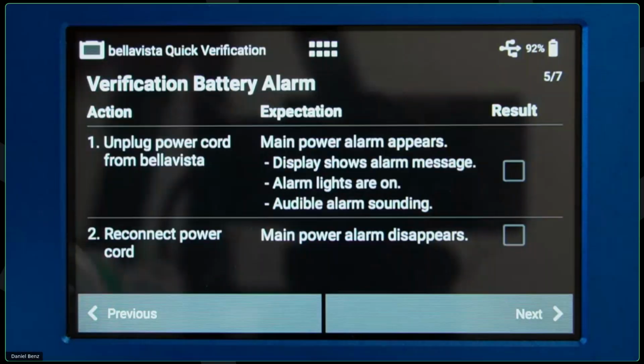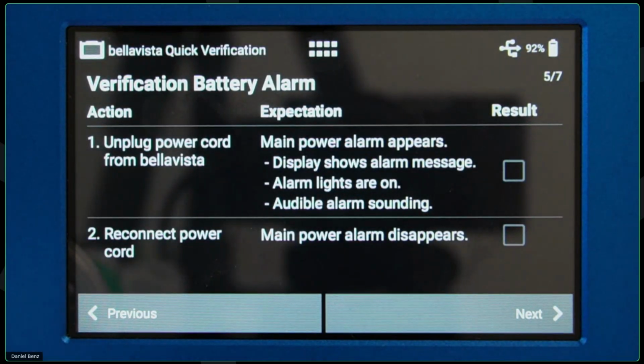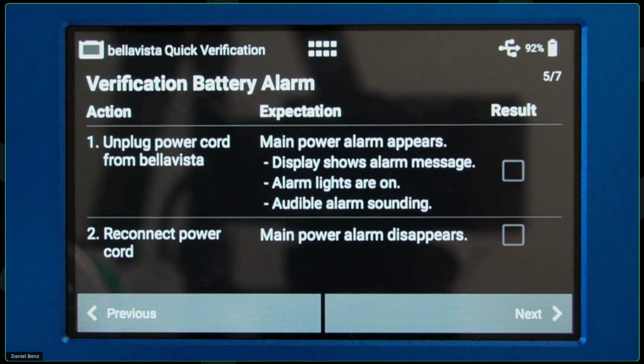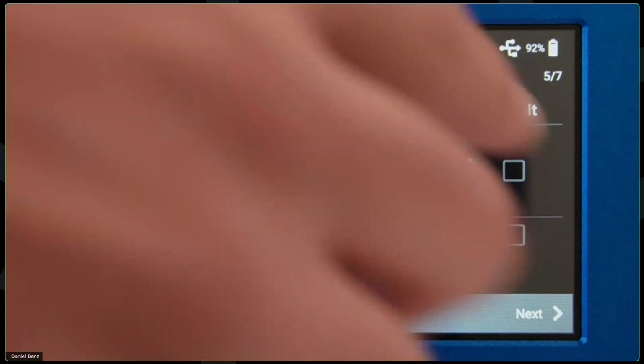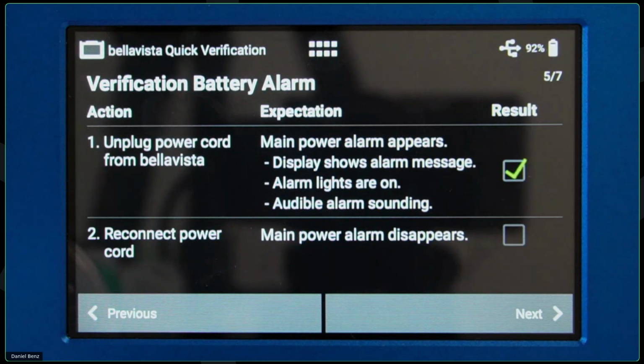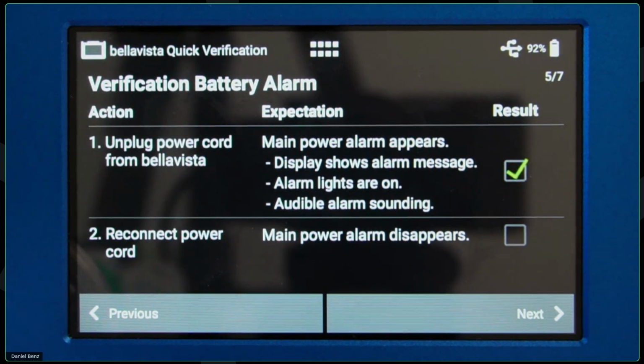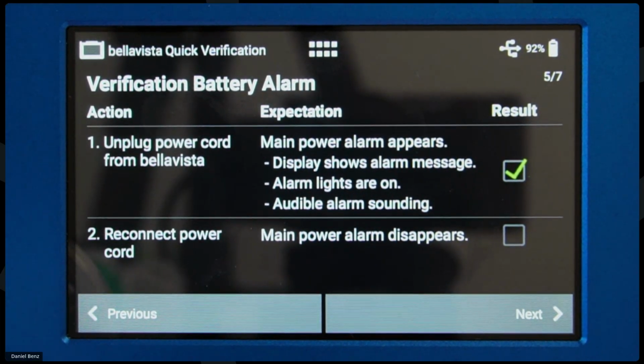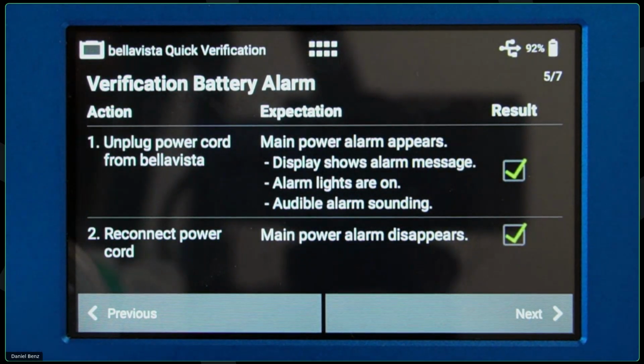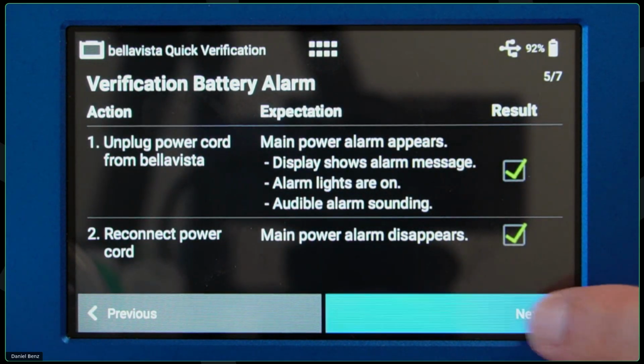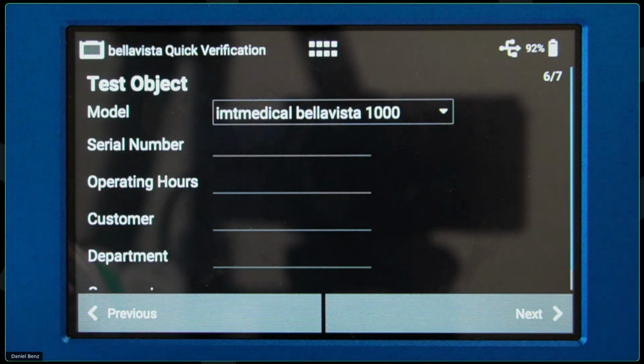Then I go next. In this verification here, it also asks me to unplug the mains power cord. And of course, the device should run from battery and trigger an alarm. That happened. Then I connect it back and it should recognize mains power. That happened as well. So I can confirm on the screen here that that happened. Then this can go on for many different pages. Again, it all depends on the service manual we are mirroring here.